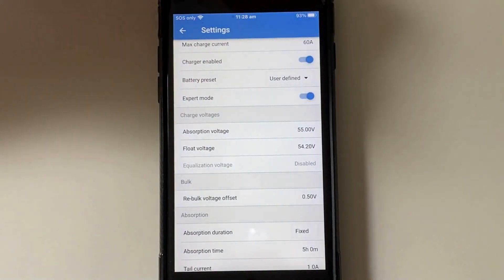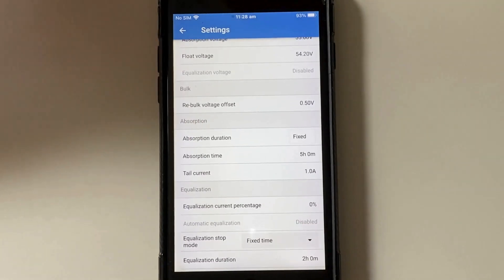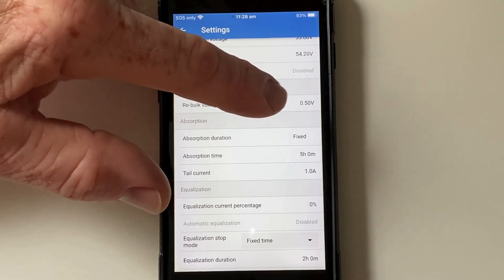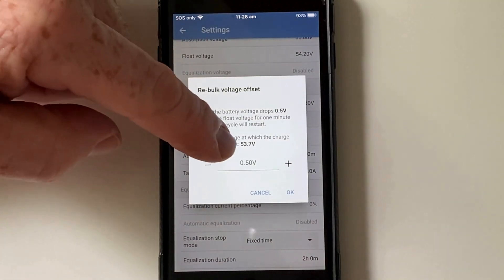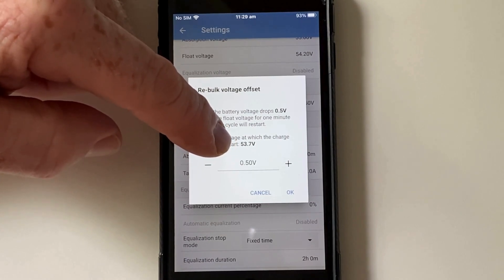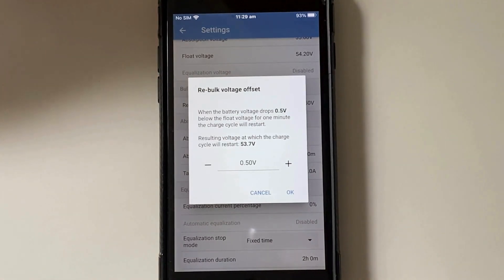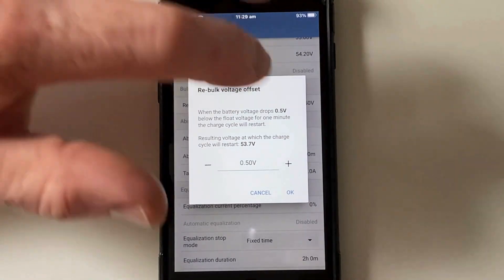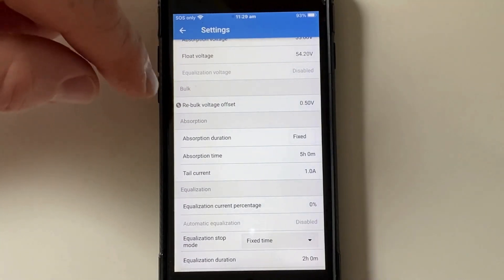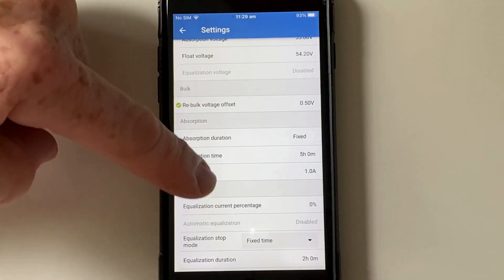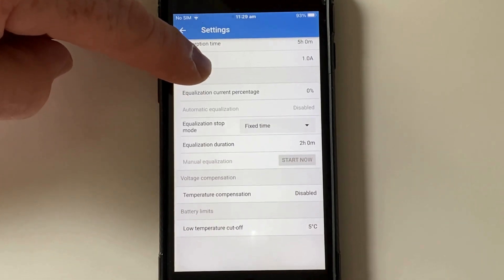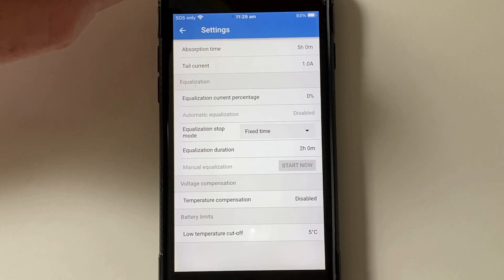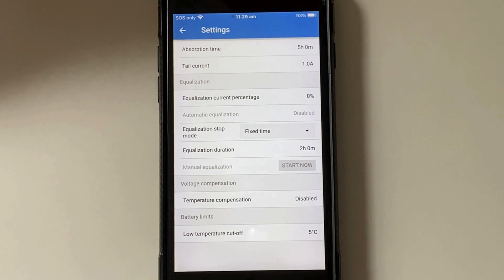We can go into expert mode here. I have my re-bulk set at 0.5. So during the day if I have a high load and my battery drains below 53.7 it will go back into re-bulk and go from either float or absorption back into bulk charging. That works best for this system. If we get a little bit of cloud and I've got the air conditioners on, the voltage will drop below that point and the next time the sun comes out it's straight back into charging the battery up.